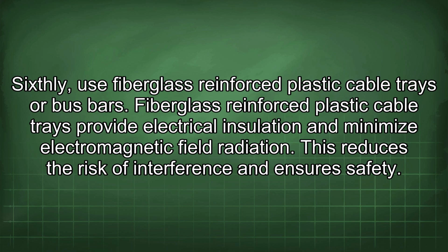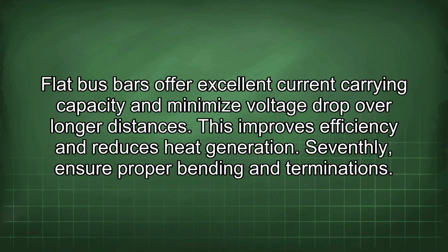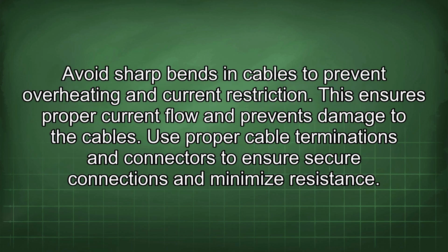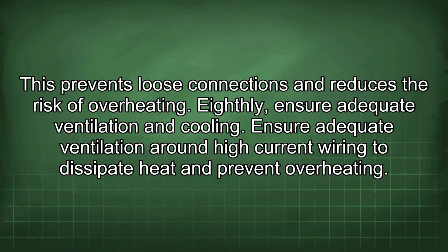Sixthly, use fiberglass reinforced plastic cable trays or bus bars. Fiberglass reinforced plastic cable trays provide electrical insulation and minimize electromagnetic field radiation. This reduces the risk of interference and ensures safety. Flat bus bars offer excellent current carrying capacity and minimize voltage drop over longer distances. This improves efficiency and reduces heat generation. Seventhly, ensure proper bending and terminations. Avoid sharp bends in cables to prevent overheating and current restriction. This ensures proper current flow and prevents damage to the cables. Use proper cable terminations and connectors to ensure secure connections and minimize resistance. This prevents loose connections and reduces the risk of overheating.